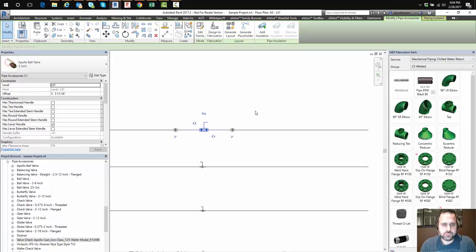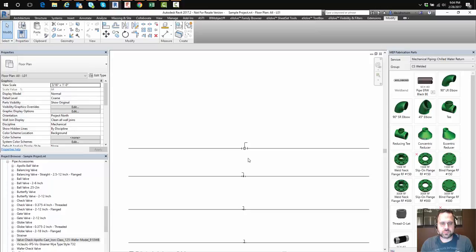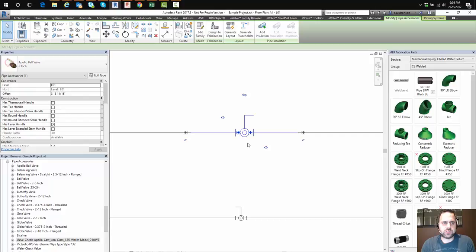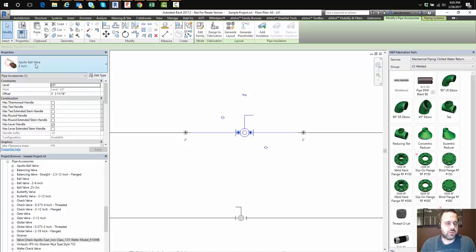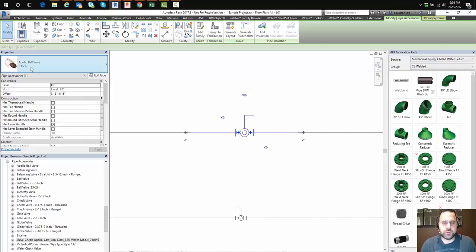Same thing is going to be true obviously for all our other types of valves here. The way Autodesk has set this up is we can map this automatically through button codes. If you look at the name over here in the type selector, you'll see Apollo valve two inch. Apollo ball valve is the actual name of the family, two inch is the type. So a type can mean a lot of different things with families. In this case it's more or less the size, the diameter. So we have to go tell fabrication that in the case of Apollo ball valve two inch, we want to put in this ball valve from our service.